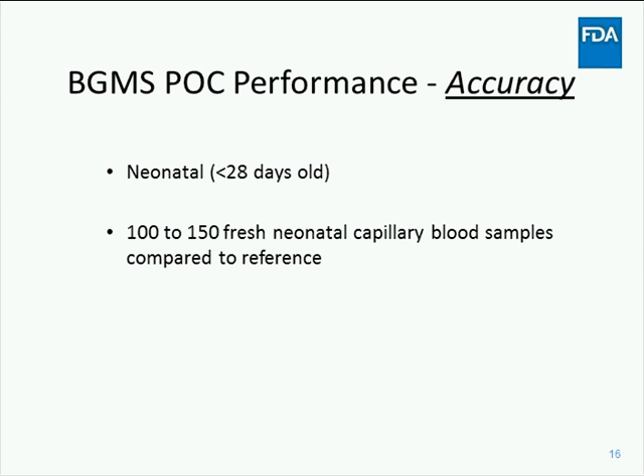If the intended use population of the device includes neonates, then a separate neonatal study should be performed to support this use. Neonatal blood is known to differ from adult blood in that it can often have higher hematocrit levels and lower blood glucose concentrations compared to adult blood. Because these differences may have a direct impact on the performance of the blood glucose monitoring, a neonatal accuracy study should be performed to validate any neonatal claim. Neonatal samples are defined as samples from subjects less than 28 days old. And for this study, the accuracy of 100 to 150 fresh neonatal capillary blood samples should be assessed by comparing meter results to the results from a comparator method.